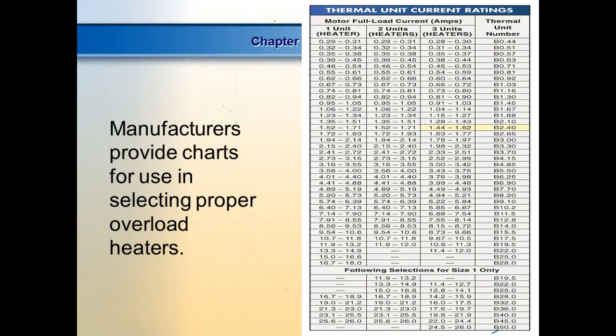So this is a typical overload chart. This would be a manufacturer's overload chart. The part numbers this manufacturer uses for their overloads start with B. So they have B0.44 all the way through B50.0. These numbers would be unique to the manufacturer. Then we have a table over here that tells us how many overloads we need. Do we need one? For low voltage single phase, do we need two? For high voltage single phase, do we need three? If we need three.